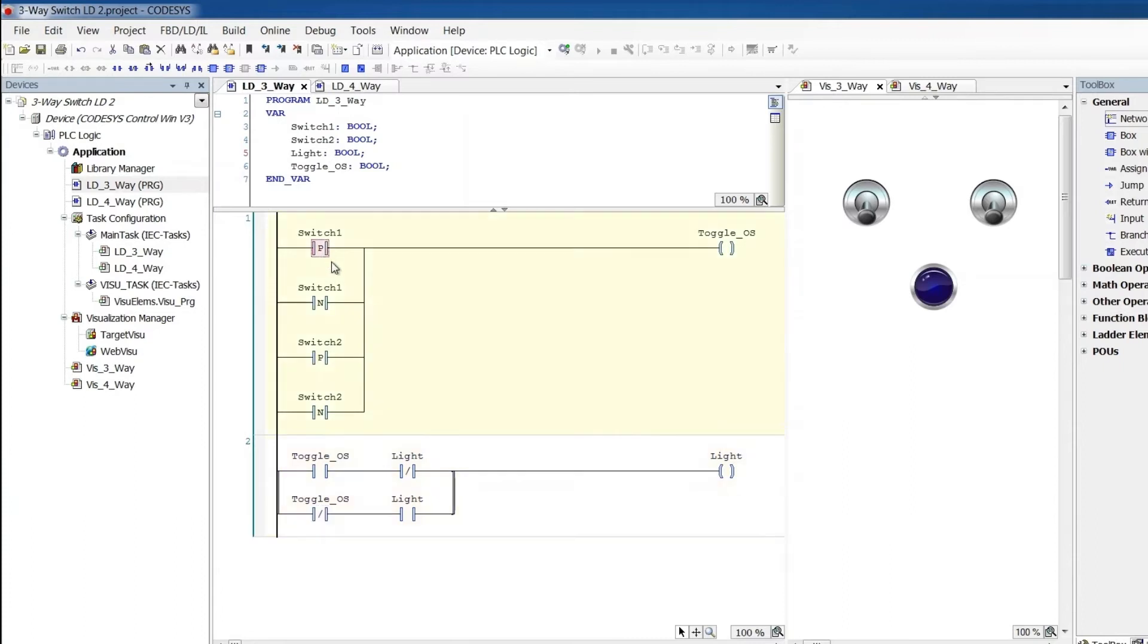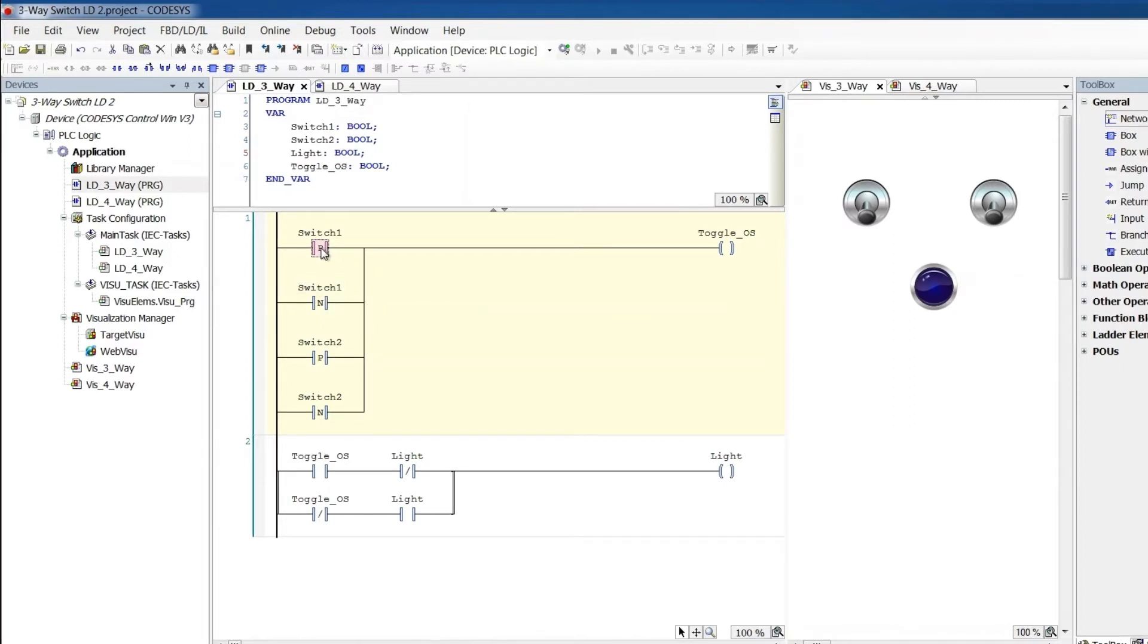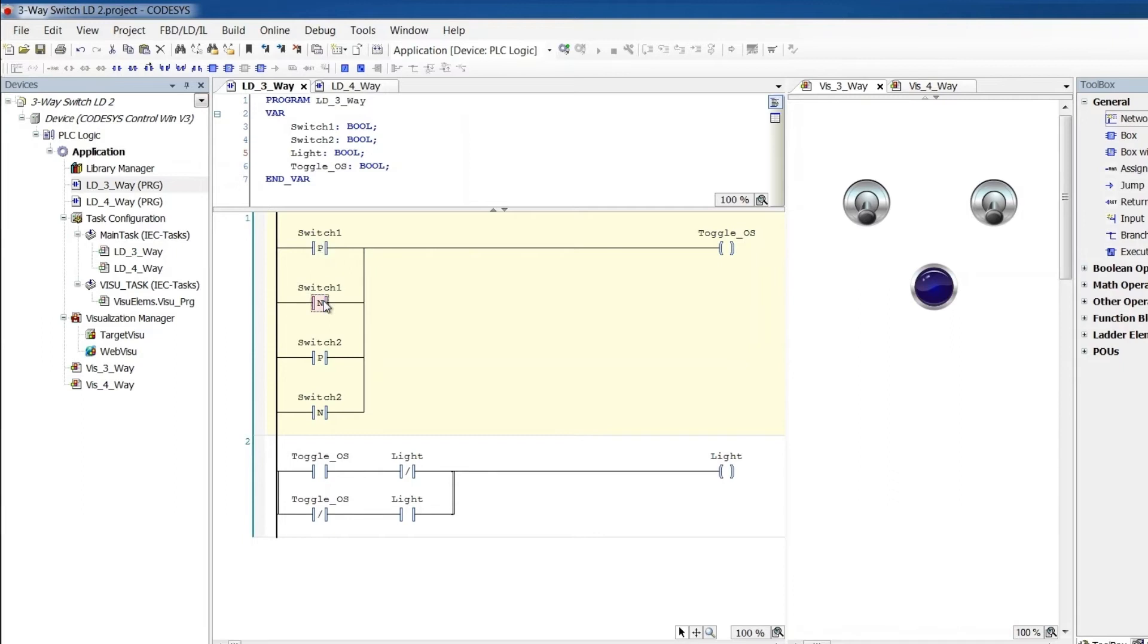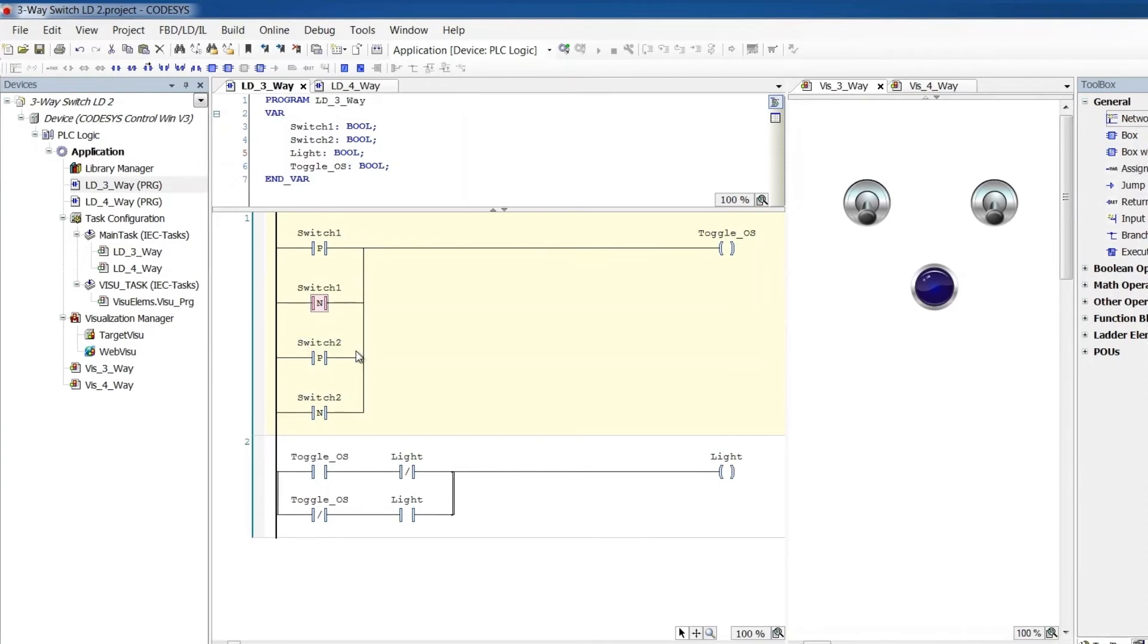So I use a rising edge and a falling edge contact for each switch here. And the P and the N in this case is P for positive and N for negative. Rising edge or falling edge is common terminology. This means that the instant that it changes from low to high, from off to on, from false to true, from zero to one, that's the positive, the rising edge. And the opposite case is true for negative edge, when it changes from true to false, on to off, one to zero.